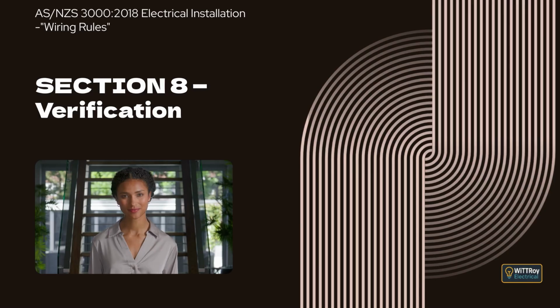Clause 8.3.6, Insulation resistance. This clause explains that insulation resistance testing is carried out to ensure insulation between live conductors and earth, or between live parts and earth, is adequate to maintain insulation integrity. The purpose is to prevent electric shock hazards, fire hazards from short circuits, and equipment damage. It also explains that insulation resistance testing between conductors is necessary for consumer mains and submains to reduce the risk of injury or property damage due to insulation breakdown.